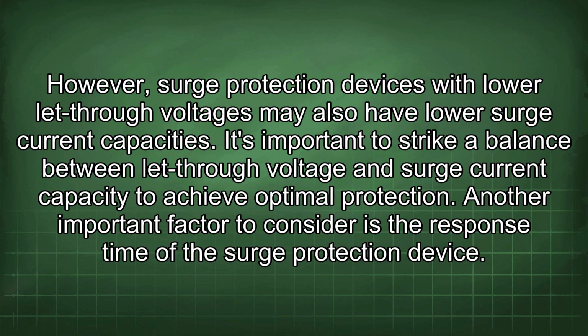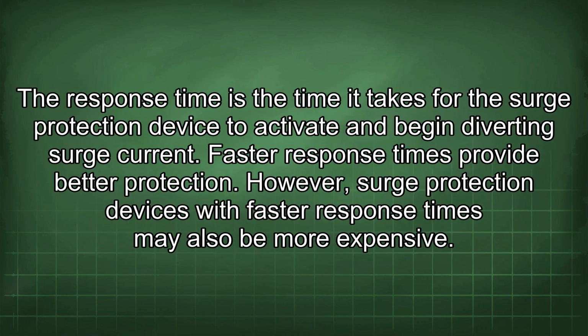Another important factor to consider is the response time of the surge protection device. The response time is the time it takes for the surge protection device to activate and begin diverting surge current. Faster response times provide better protection. However, surge protection devices with faster response times may also be more expensive.